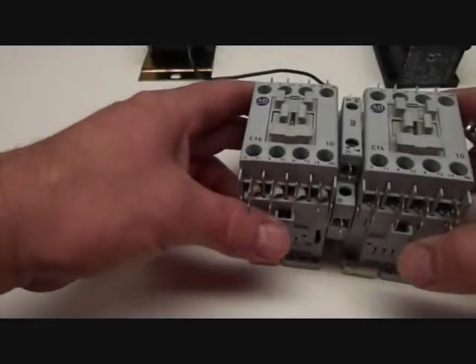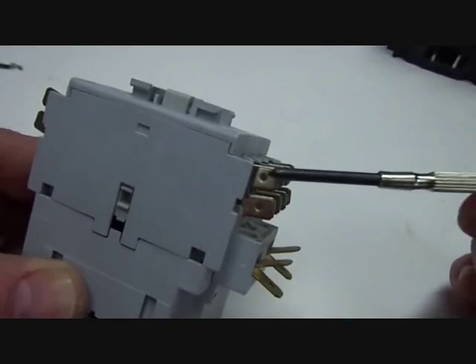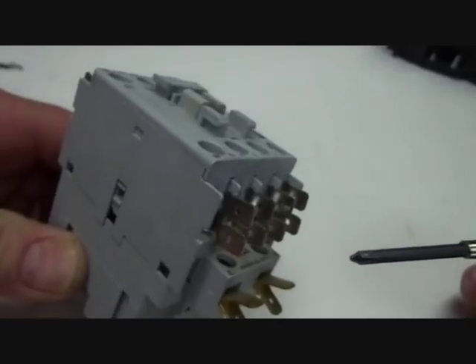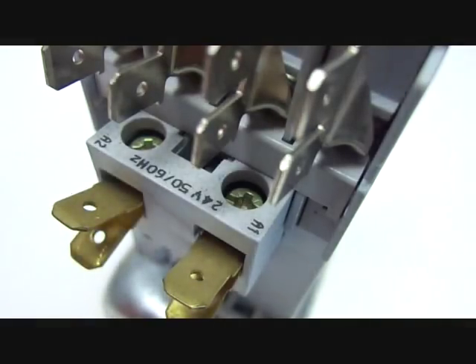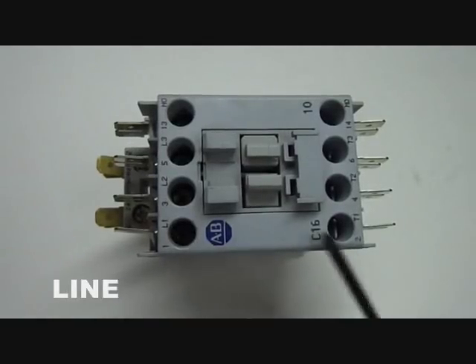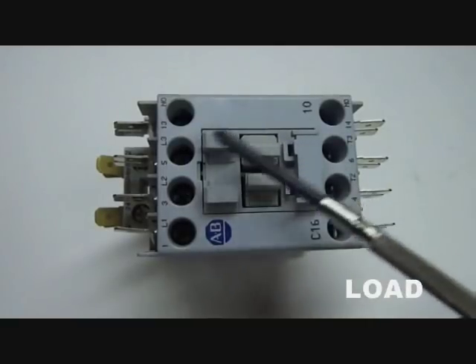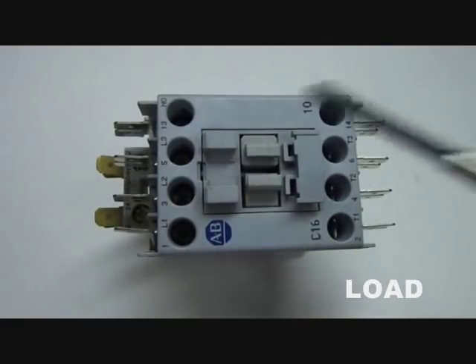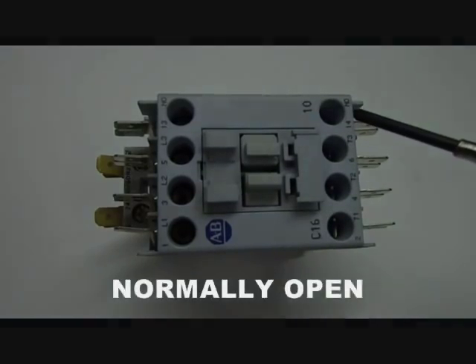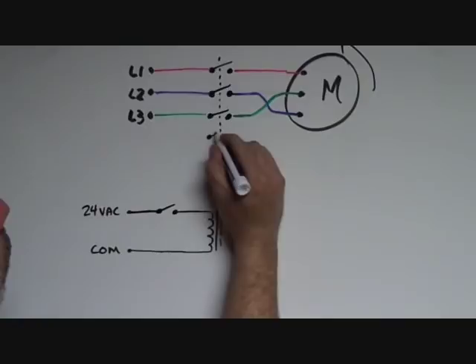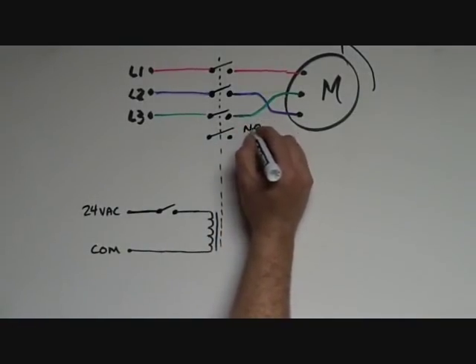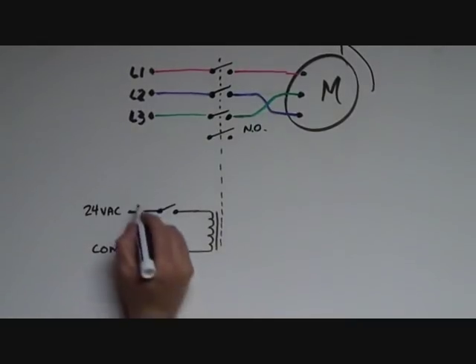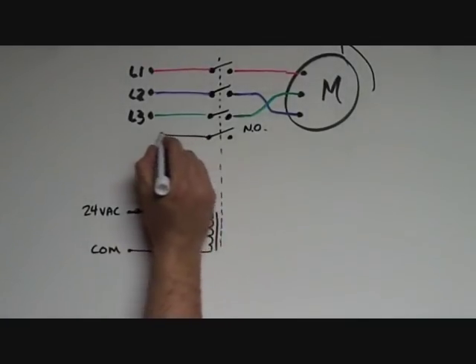Here's a single contactor. It looks like it has an awful lot of terminals, but that's because it has a spare connection point for each terminal. It has the two 24 volt coil terminals labeled A1 and A2, it has the line side terminals for the three poles labeled L1, L2, and L3, and it has the load side terminals T1, T2, and T3. I don't know what T stands for, but I know it gets hooked up to the load. This one, like most of the new ones, has a fourth pole labeled NO for normally open. It works just like the other three poles, but it's not always rated for the same current as the other poles, so you do have to be careful. This fourth set of contacts is usually used for something in the low voltage circuit.